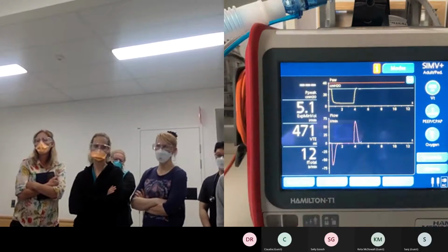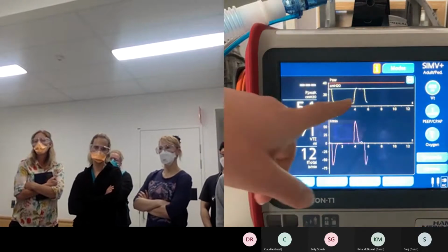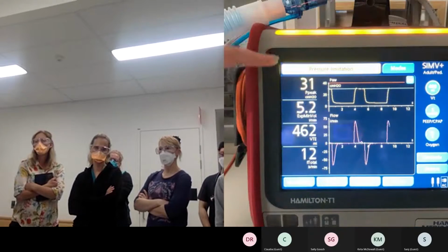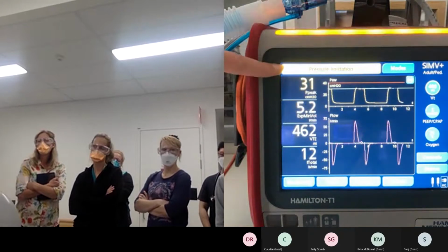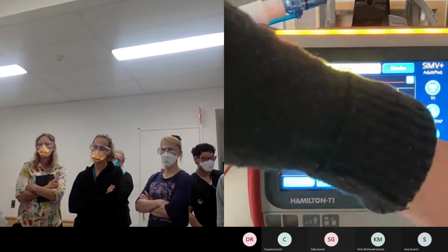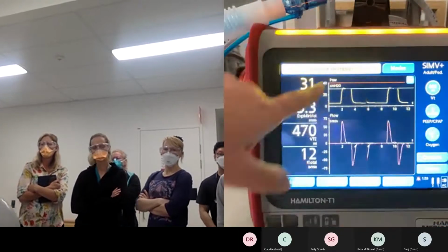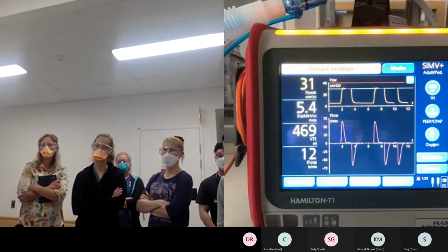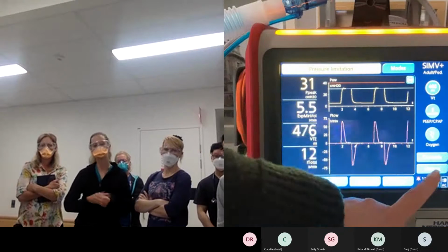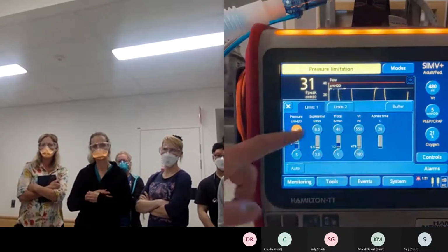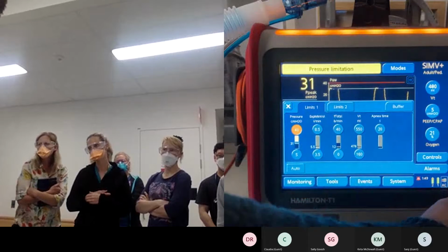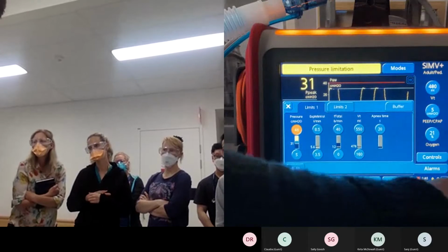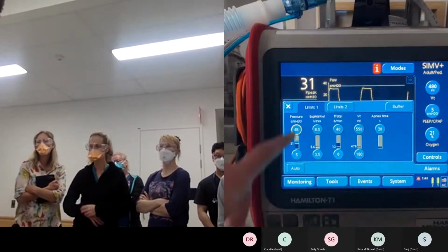Try and trigger it off actually. But you're still getting the length of the breath. You get an alert telling you that you've hit your pressure limitation, but you can see that we're still delivering the breath. Okay. If you've got a patient that you're happy to deliver a higher pressure for, you could come into your alarms, touch on that, and say you wanted to go up to 35. You dial that to 45 and hit confirm.